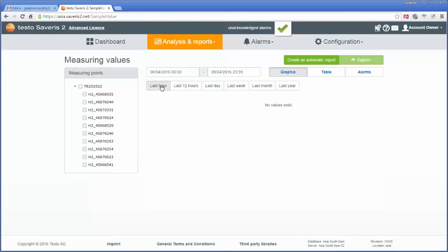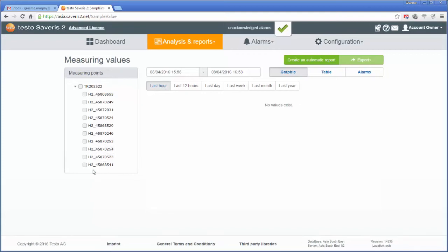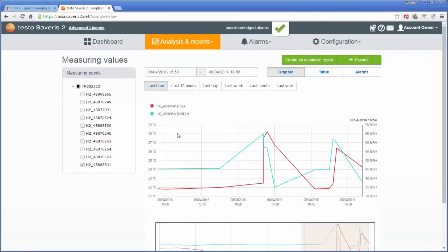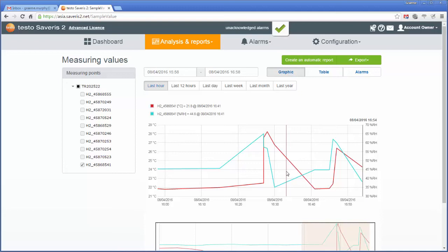So if we go in the last hour, you'll see that this will be the most recent value from it. And, hang on, we'll just click on, oh sorry, I haven't picked a particular logger, there it is there. And yeah, so we're getting readings, it's 23 degrees currently. So I put it in a nice hot spot, I'm sitting on it, now it's gone above the alarm point.